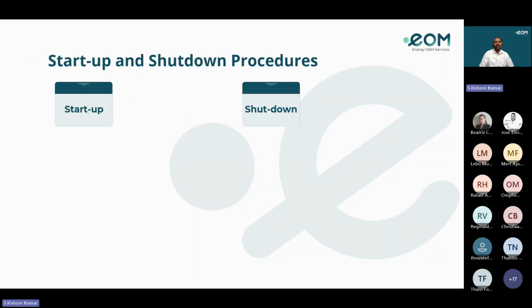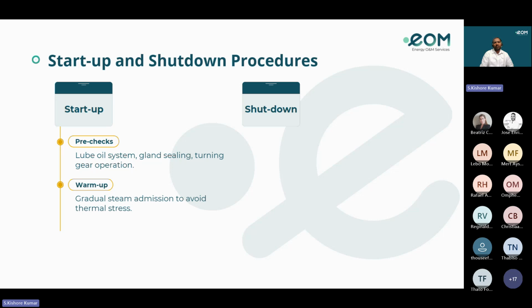Coming to the startup and shutdown procedures. In the startup, there are pre-checks: whether the lube oil system is running, whether oil pressure is there or not, and also the gland sealing steam pressure, the gland sealing temperature, and whether the turning gear is in operation or not. So that is the pre-check, and then the warm-up.